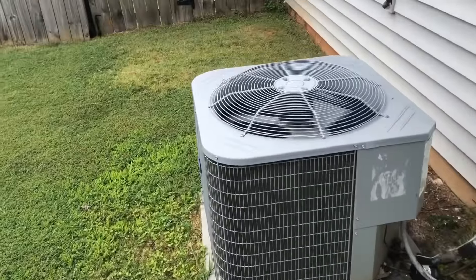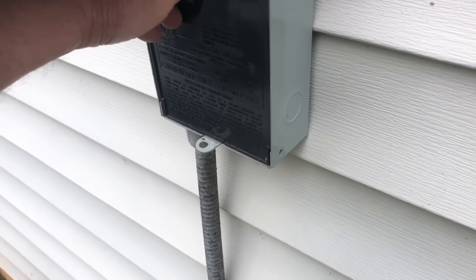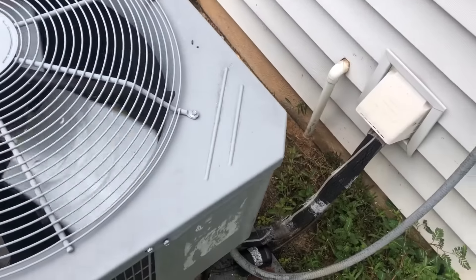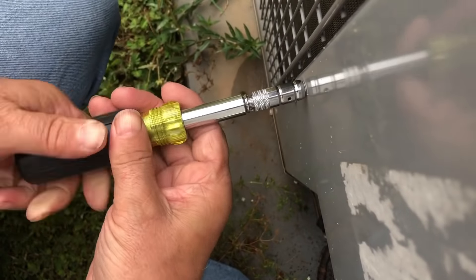Alright, no cooling. This is a new customer — we have not been to this house before, so no idea what's here. Let's go find out. Heard the death buzz as soon as she turned it on, so it's probably going to be a capacitor — one million and one.